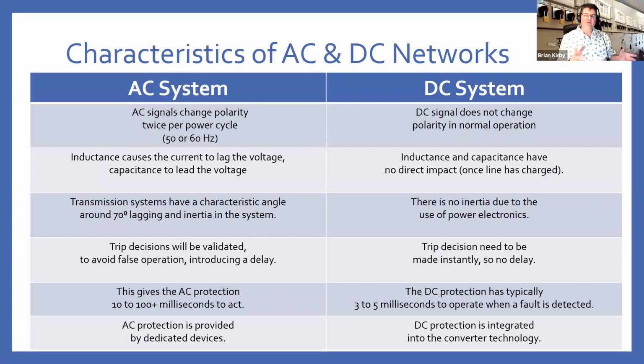On an AC system, you typically, in the UK, see an angle of about 70 degrees lag. And there's also a bit of inertia in the system due to the rotating machines that are driving the generators. On DC systems, it's all power electronics, and there's no inertia as a result. It's all pure active power.